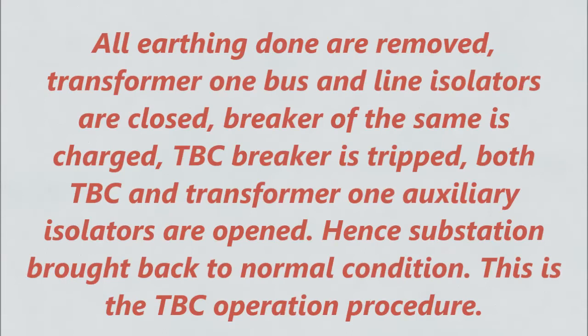That is, all earthing done is removed, transformer one bus and line isolators are closed, breaker of the same is charged, TBC breaker is tripped, and both TBC and transformer one auxiliary isolators are opened. Hence the substation is brought back to normal condition.